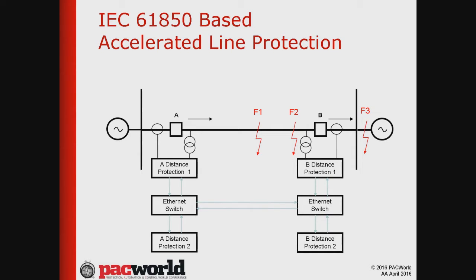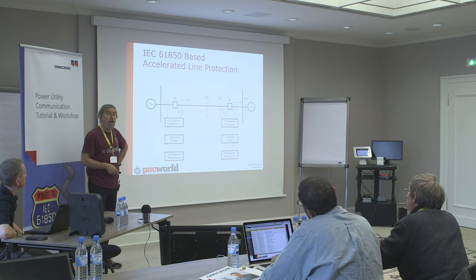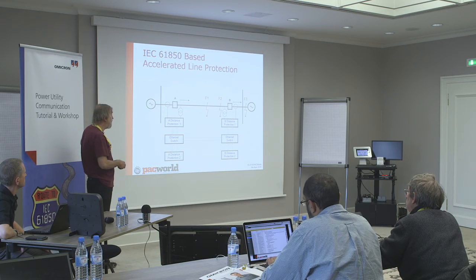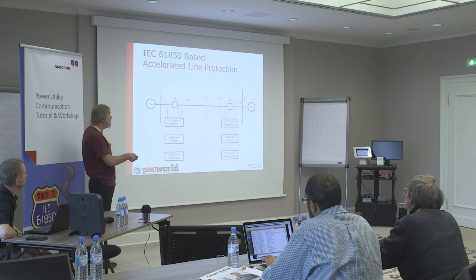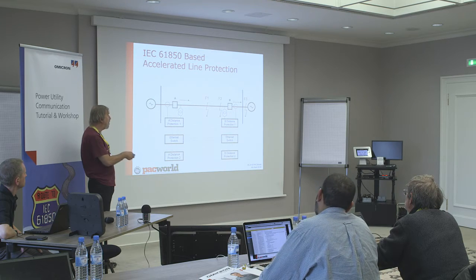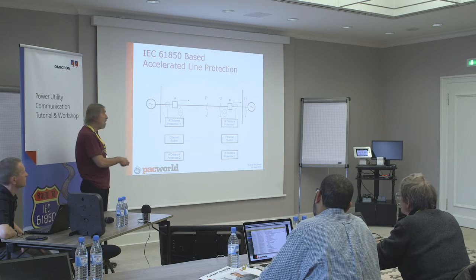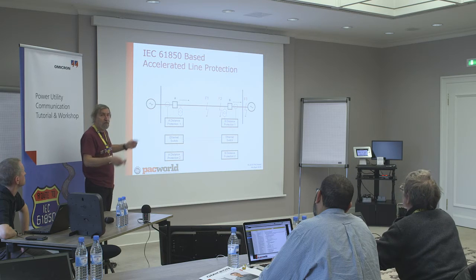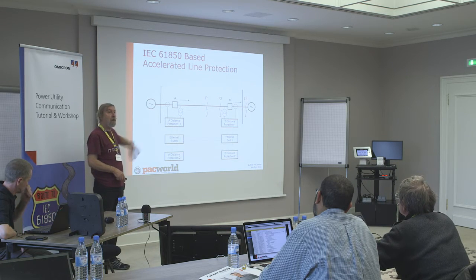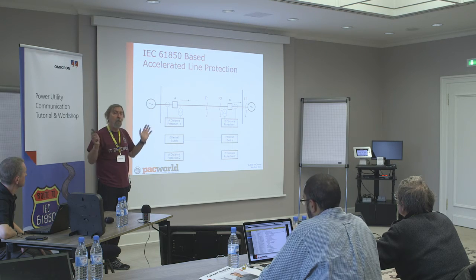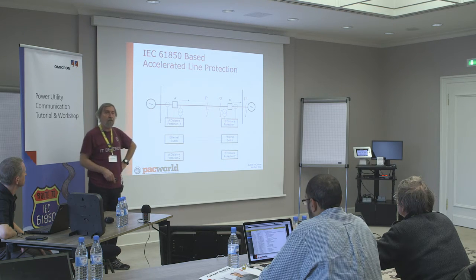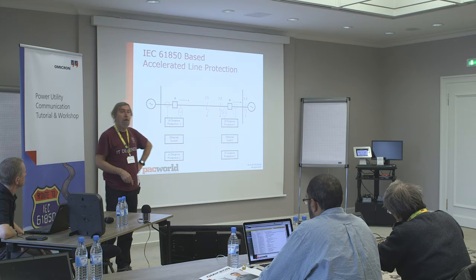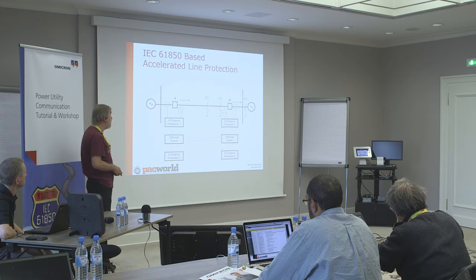The problem with these accelerated protection schemes is that they require a communication interface between the two substations. And this is something that when it is a dedicated channel, it becomes quite expensive. So in conventional substations, we may have a direct interface between the two distance protections. In IEC 61850, we may do what we call tunneling using direct interface between Ethernet switches at the two ends. But this still is a quite expensive solution. And people may say, we don't have the money to do accelerated protection using fiber on all the transmission or sub-transmission lines in the system.